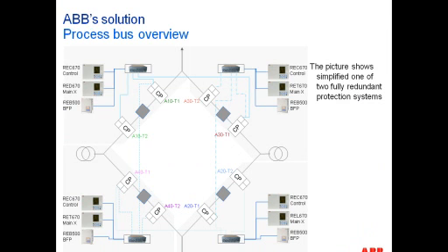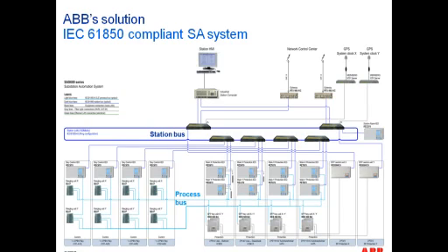Okay, in our particular system, the whole system was actually redundant. So when we look at the architecture, we have 2 networks. We have the process bus network close to the process, and then we have the station bus network for 61850-8-1. So essentially, as we can see, we have this process bus network which is connected to the different CT sensors and the different merging units, which are used to publish all the different current and voltage values out of our ring bus installation.